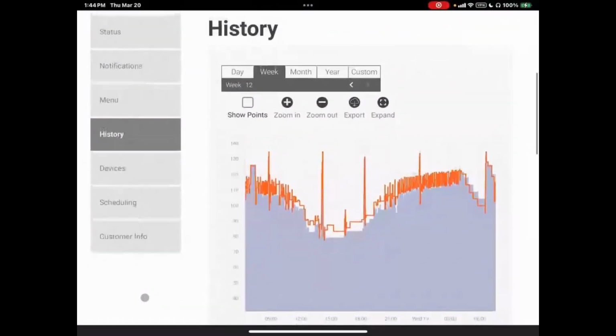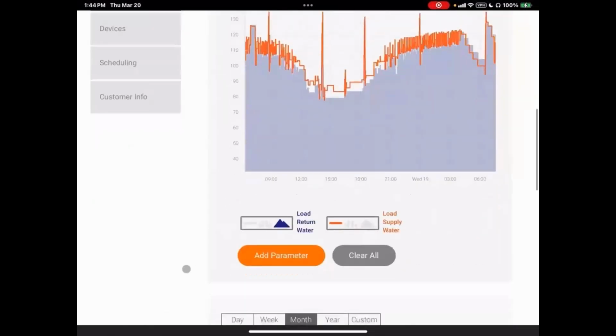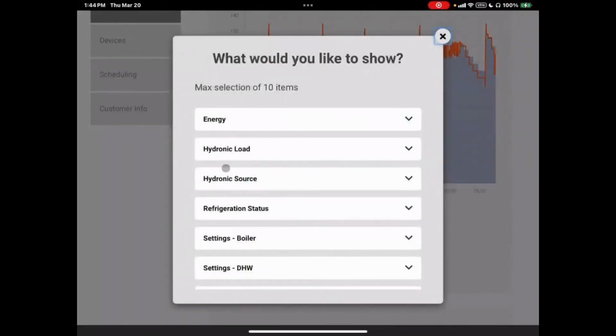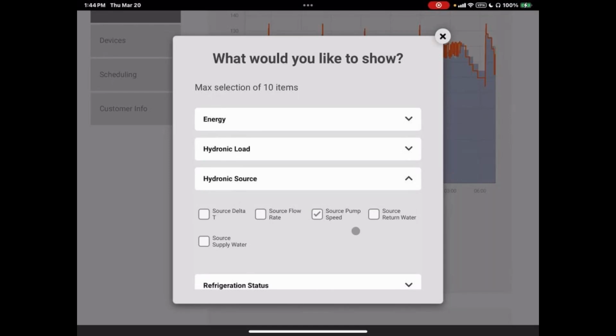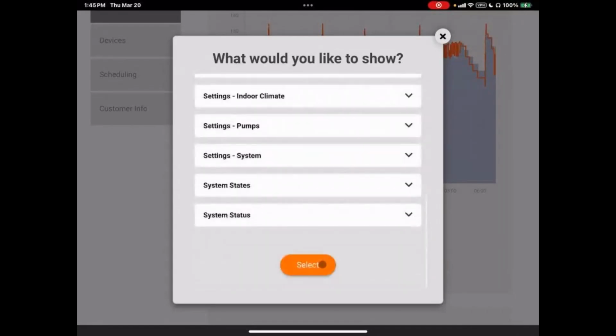John, in all your experience, having a tool like this that could actually show you all of this detail over a large time period, I'm sure would have made it a lot easier to figure out some issues when it came to water flow or delta T's on certain zones and things like that. Yeah, absolutely. I mean, the instrumentation that you would need to get this type of data, BTU meters, temperature sensors, data loggers, is hundreds, if not thousands of dollars of equipment. So, I've not seen all this detail before, Justin. I'm amazed at how flexible that graphing is, to go in there and really diagnose what's going on with that heat pump.